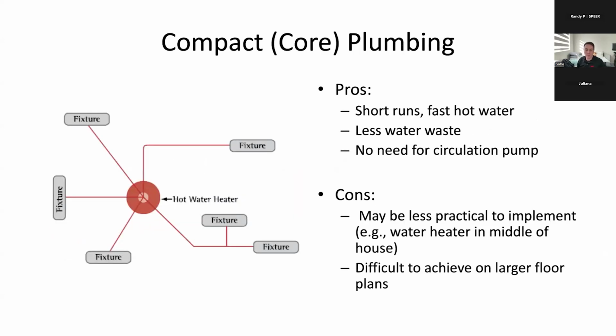Another type, which we're seeing in energy codes and which is becoming sort of the gold standard, is what they refer to as a compact plumbing design. In some states, you get an energy credit for building a home with a compact plumbing design. Now, what does that mean? It means that the water heater is more centrally located in the house, and that the plumbing runs to each fixture are not going to be more than about 20 feet or so of half-inch or three-quarter plumbing.